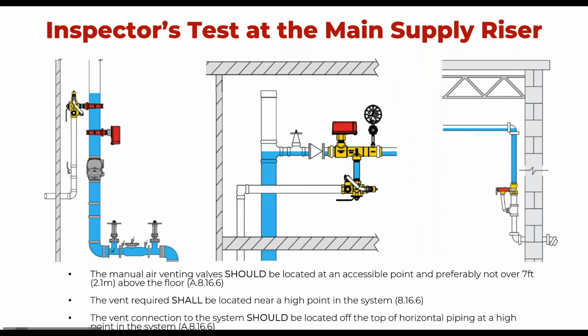Typically, inspector's test valves make extremely poor combination air vents because the inspector's test valves could be located at or near the inbound supply, or they're also often combined with express drains, so they're fed from the bottom of the pipe, again, not off the top of the pipe. Or if they are used in a remote inspector's test location, very rarely is that fed from the top of the pipe.